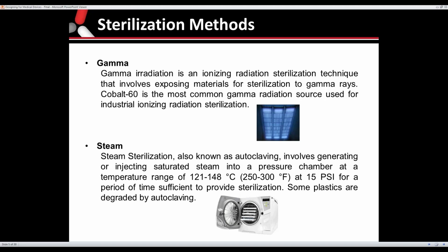Steam sterilization is another very effective way to sterilize medical components, and higher heat steam sterilization is autoclaving. One of the most important things with autoclaving is to understand the heat deflection temperature of the material that you're using for the device, so that you don't have distortion or warpage or even material starting to melt at the autoclave temperature. So it's just important to understand whether or not your material is compatible with steam or high heat steam sterilization, such as autoclaving.